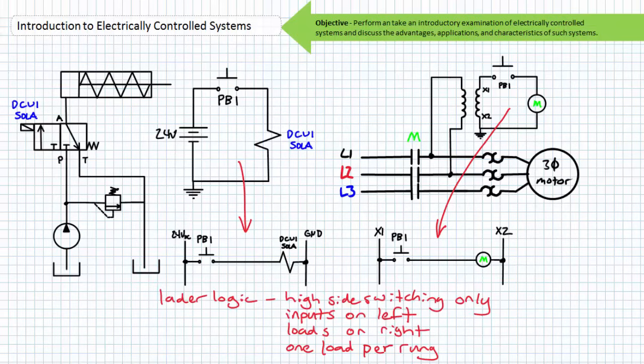This implies that ladder logic diagrams always use high-side switching arrangements and that input devices like switches are placed between the high side and the electrical load, be it a coil or solenoid, and the low side or grounded upright rail. Switches on the left, loads on the right. The one exception to this rule are the normally closed overload contacts associated with a motor starter, which we'll discuss later. Again, ladder logic is a means of flattening out a traditional electrical schematic into a readable line.